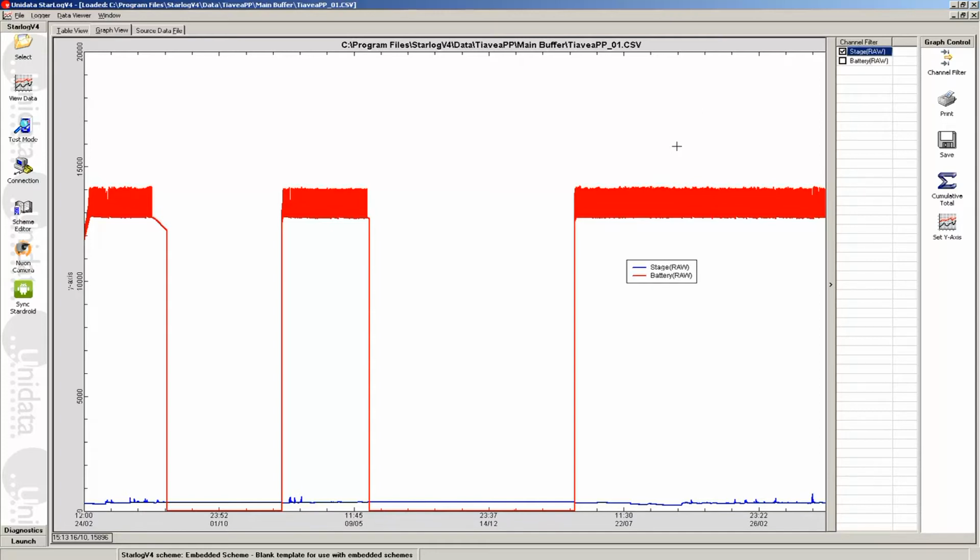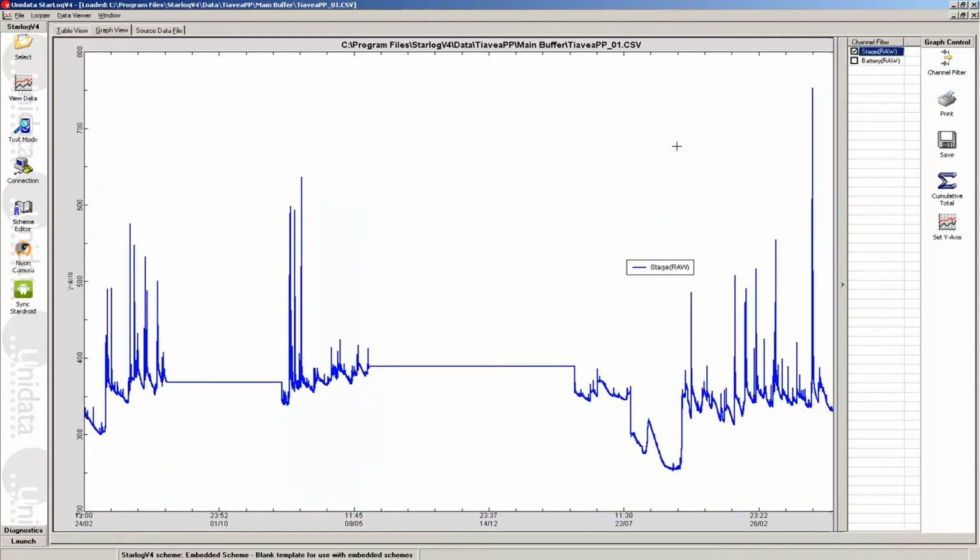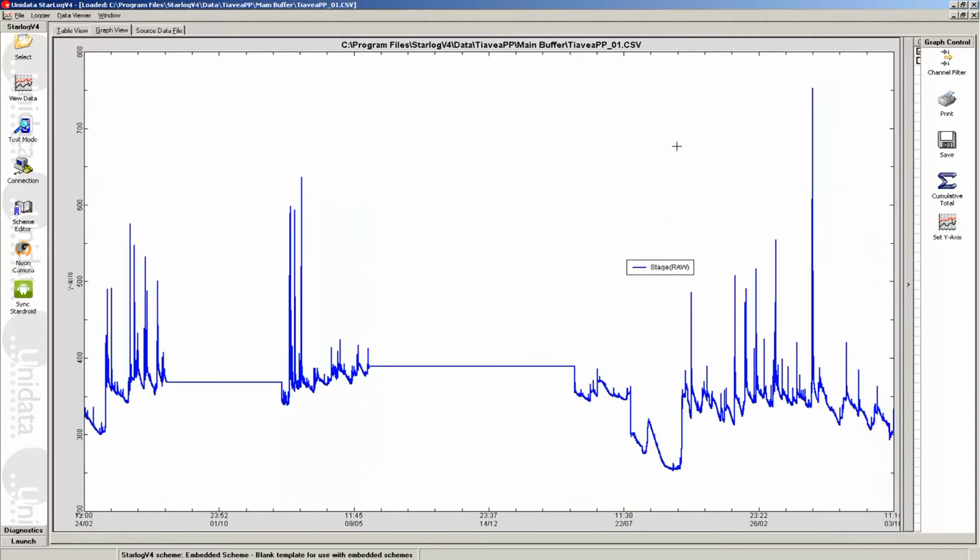Yes, this site had the battery stolen on 2 occasions. Hence, with no power, the pump process stopped over this period. You can see this in the 2 straight lines. And another concern here, when the record does start up, there's this period here, looks like an offset needs applying, or a transform on each end of this section, which will raise it up and bring that right, and that record from then on looks pretty good.